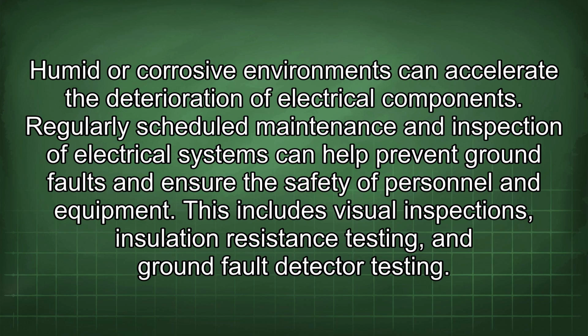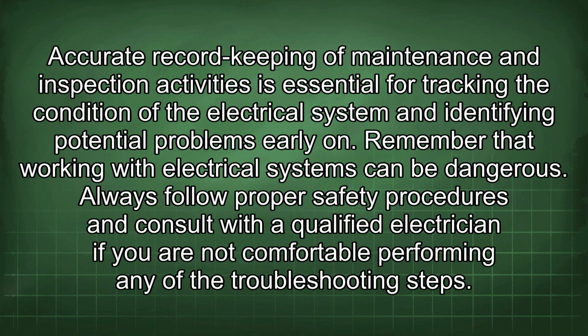Regularly scheduled maintenance and inspection of electrical systems can help prevent ground faults and ensure the safety of personnel and equipment. This includes visual inspections, insulation resistance testing, and ground fault detector testing. Accurate record-keeping of maintenance and inspection activities is essential for tracking the condition of the electrical system and identifying potential problems early on. Remember that working with electrical systems can be dangerous. Always follow proper safety procedures and consult with a qualified electrician if you are not comfortable performing any of the troubleshooting steps.